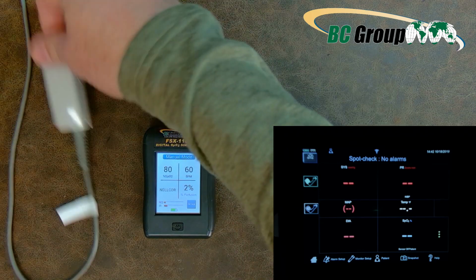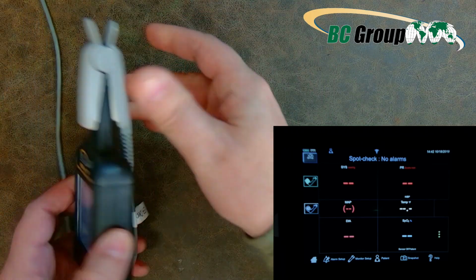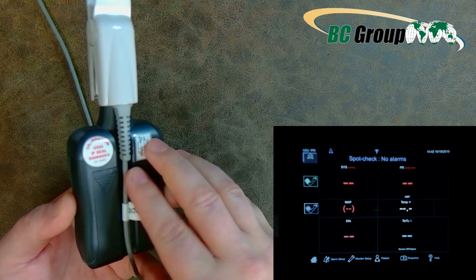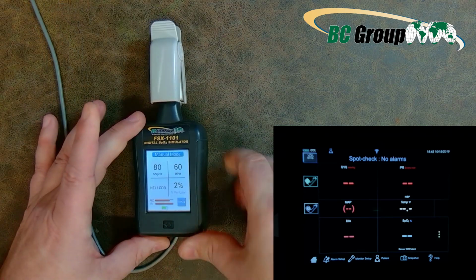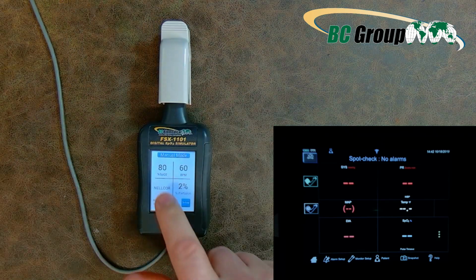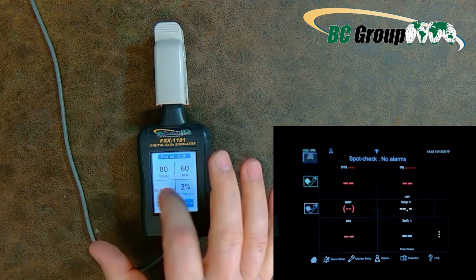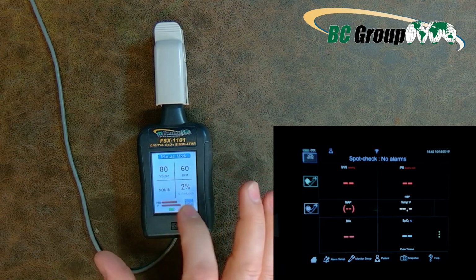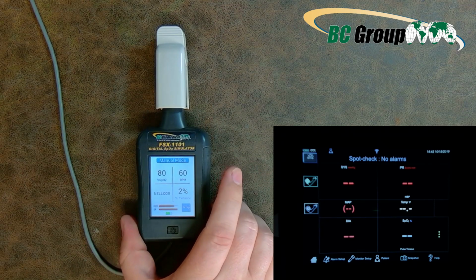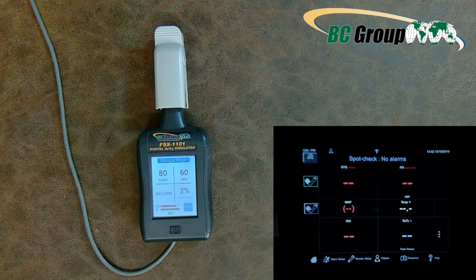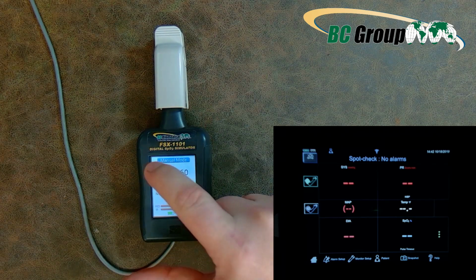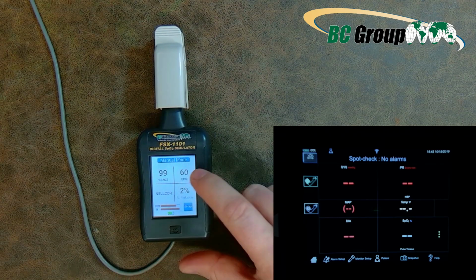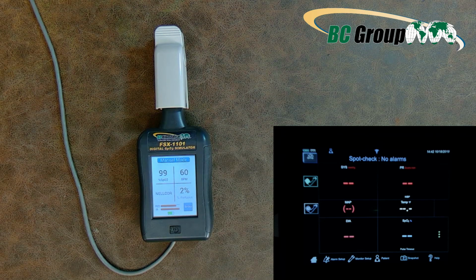perfusion. We're going to take the finger probe, install it over the artificial finger, and make sure that the cable runs down the channel in the back of the unit. Select your finger probe according to what model you're utilizing. I'm using Nellcor. We're going to start out with an SpO2 of 99% and a 60 BPM. You should see it take pretty quickly over on the patient monitor in the corner.